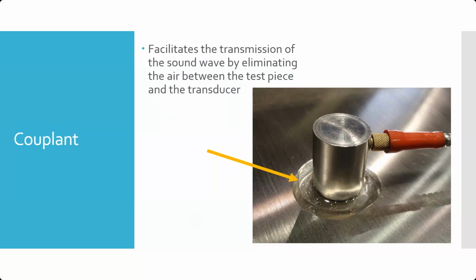Well, you're calibrating, so can it mess up the signal? If you had air pockets in there, that would mess the signal up even more. And so part of your setup of your tester is you're calibrating where that point is. You're going to set something called the offset, where the zero offset is where the sound wave actually is entering the part. And any of that distance between, because yes, there's a thin layer of that gel in there, right? So anything that is above the surface of the part on our display screen, we're essentially going to shift the whole display and just put it off the side of the screen where you don't even see it. And so we take that into account as part of the setup process.